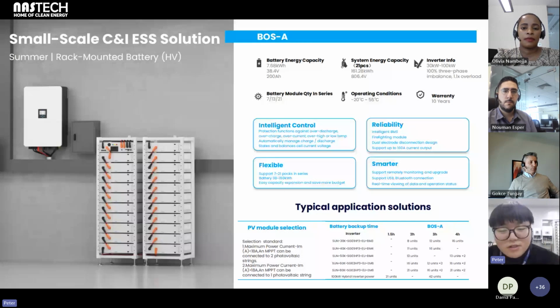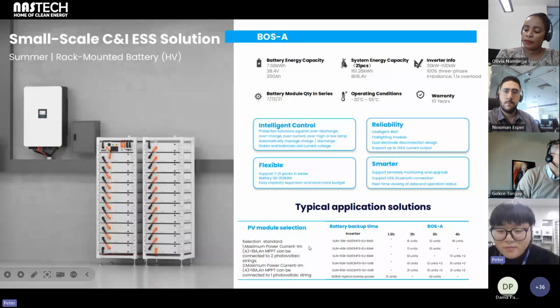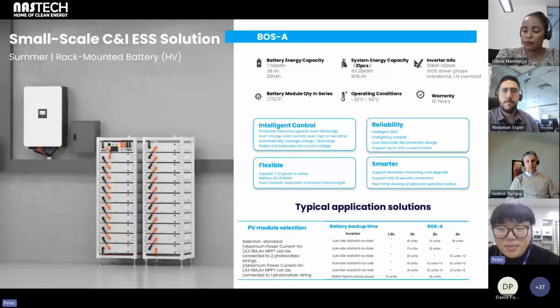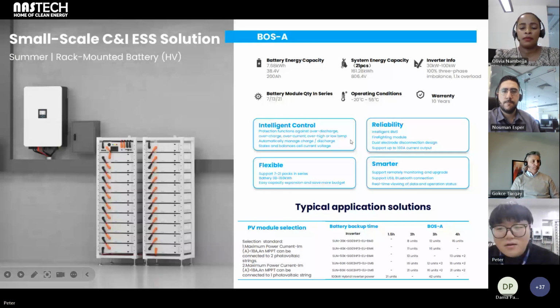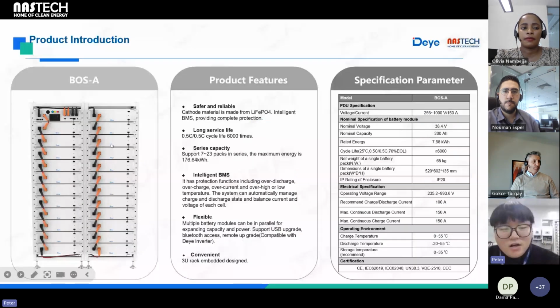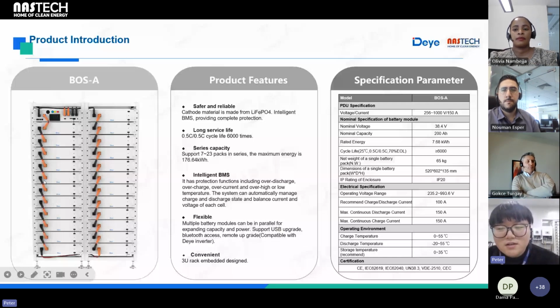The BOS-A battery can not only fit our 80K inverter, it can also be used with the 30 to 60 models. We can change the case size and the cluster size, and you can have a different voltage solution for the battery. So it's very flexible. For this battery, each unit is 7.68 kilowatt hour, and the nominal voltage is 38 volts for each module. Inside the battery, we are using EVE cells, so it's also a top brand in battery cells. And the recommended charge and discharge current for one cluster is a maximum of 100 amp.